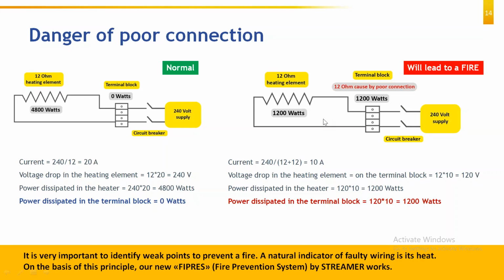The terminal block is not designed to withstand such a large amount of heat, and that is why the contacts at the terminal block will eventually burn, or if there is fuel near that contact, it will definitely catch fire. So this is the danger of a poor connection, which is there in every circuit basically. We have taken the example of a terminal block. A similar voltage drop can occur at the terminals of a circuit breaker, and if this happens, either your circuit breaker terminals will burn, or if the spark is a little bit higher, the whole circuit breaker may also burn. So it is really a big danger.